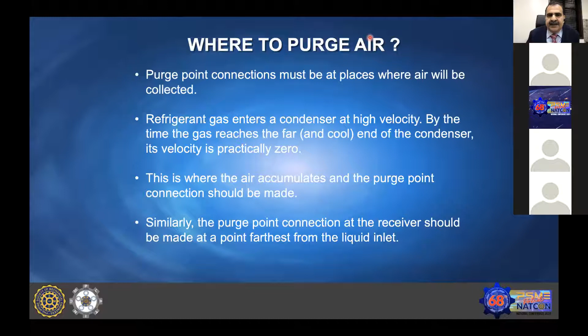Now, if we have a condenser, the question is always asked whether we should purge air from the receiver or the condenser. In my opinion, the purge point should be connected from both places, but you need to understand that air will remain in the condenser when the receiver temperature is higher than the condenser. That is, if the receiver is placed on the warmer side or the open side and is directly exposed to the sun, it may happen that the receiver temperature is warmer than the condenser temperature. Then air will not enter into it.